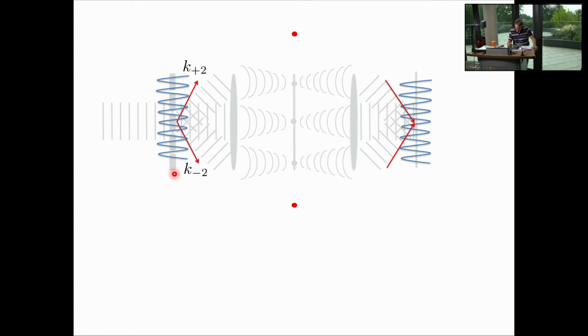As soon as the frequencies get high, frequencies in the object that are very high, so this is already high frequency content that I need to faithfully recreate the square wave, these high frequencies will diffract the light out to angles that are extreme. And as soon as these angles are larger than what the objective lens can capture, we don't transmit information through the microscope anymore. And so, of course, the maximum angle is just given by the numerical aperture, right?